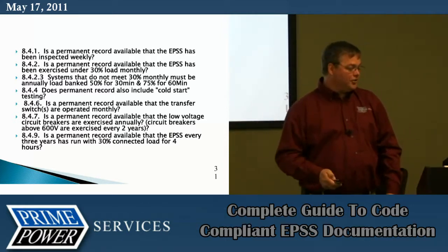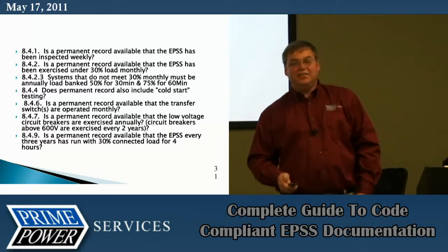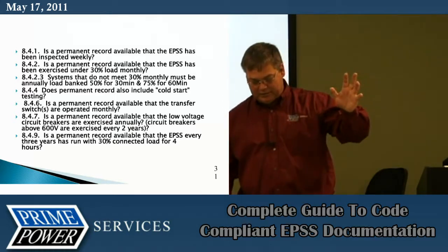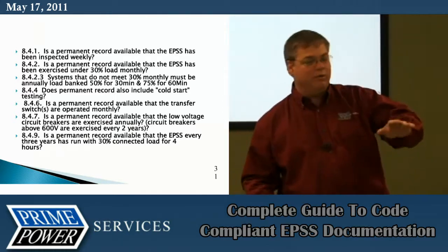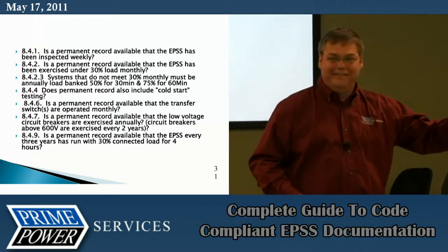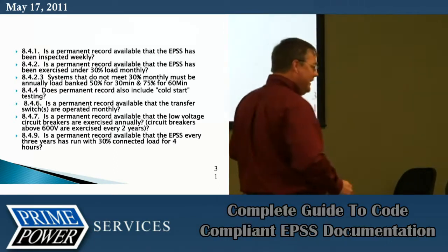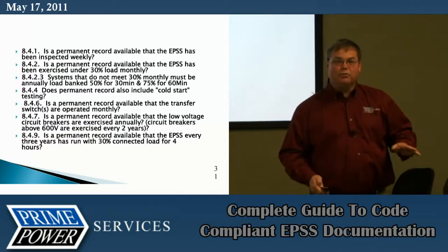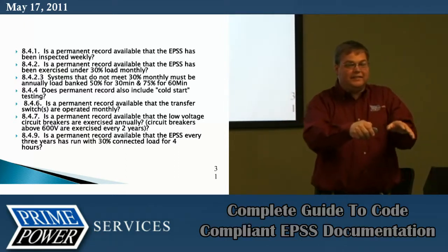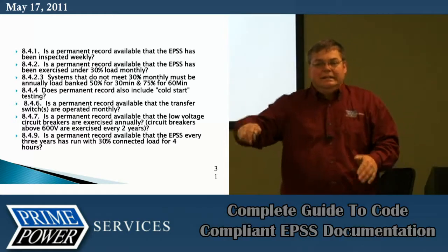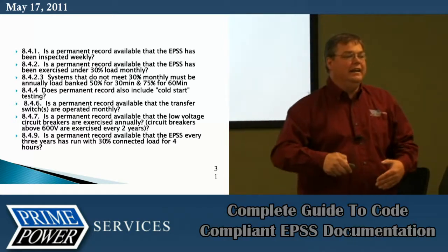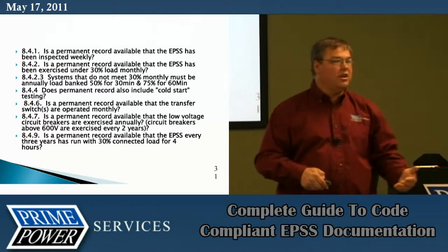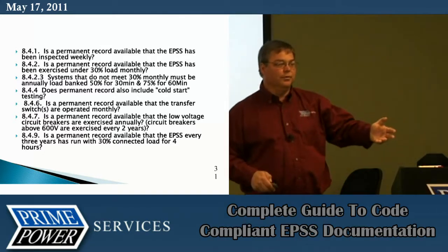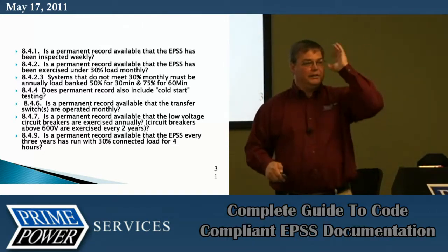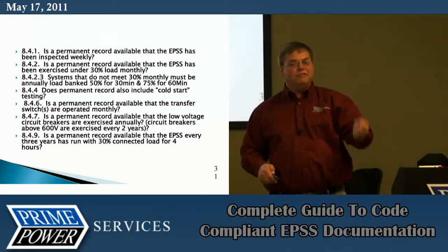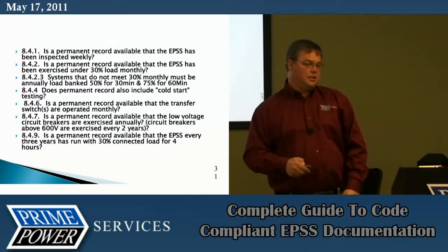Does the permanent record also include cold start testing? This doesn't mean, and this is my opinion, without the block heater. This means starting from scratch. In other words, the intent of that standard is they don't want you to fire this thing up, let it get hot, cut it off, and then do your monthly test. They want you to cold start it from scratch - fire it up and put the load on it right away. That's the cold start portion.